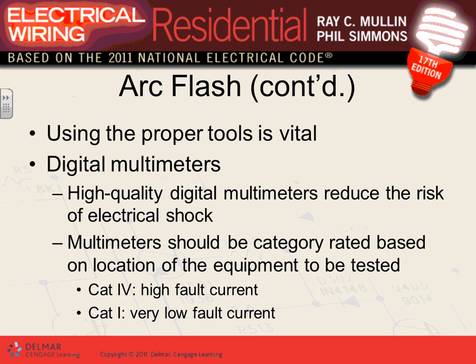Using the proper tools, guys, is vital. There are categories of meters, category 3 and category 4. This category 4, the high fault current one, is the only category you can use on the line side of a disconnect.